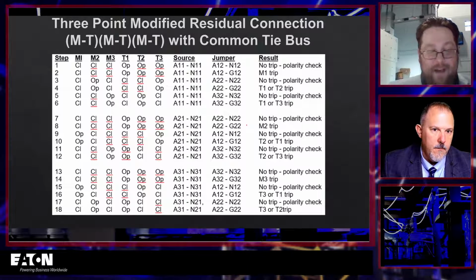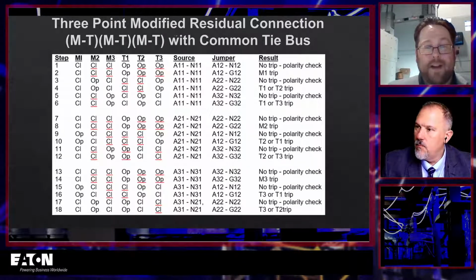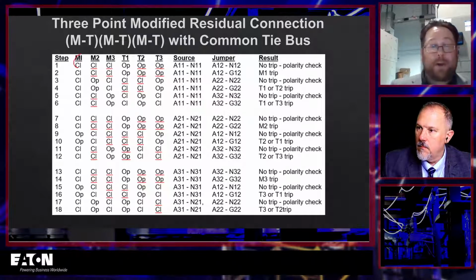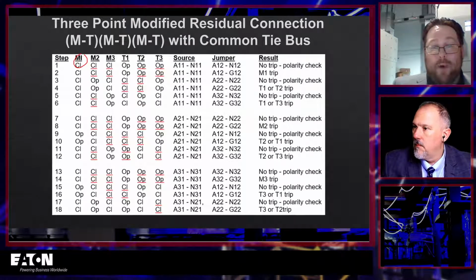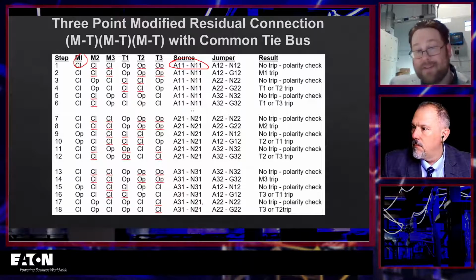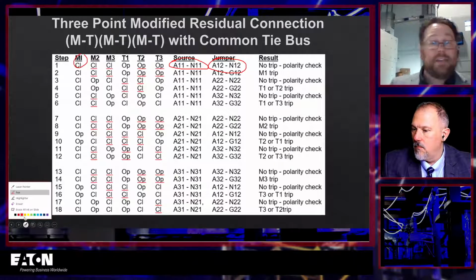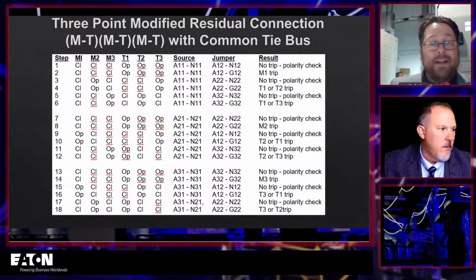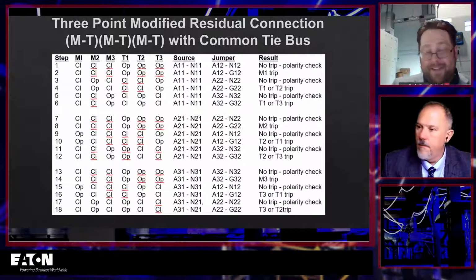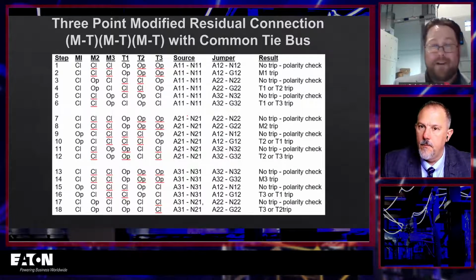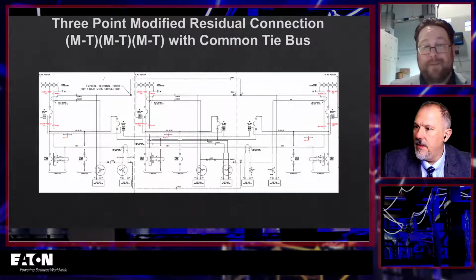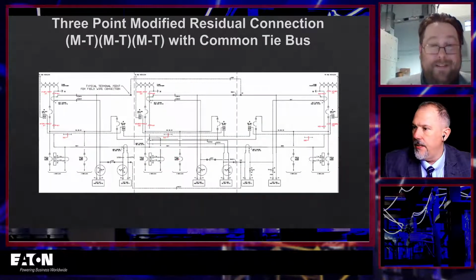So this is identifying the position of your breakers. Are they open or closed? That's what the first columns are: M1, M2, M3, T1, T2, T3. Then what you're going to inject current onto, so A1 and N1, those breakers, those buses, and where you need the jumpers to have the current flow back through the sensor properly. And what your expected result would look like, trip or no trip. In this case, with so many mains and ties, what breakers do we expect to trip? Right, and this is the basic arrangement for that scenario.